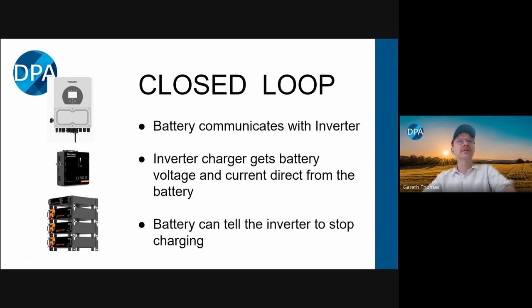The advantage in doing this is that when you're in the middle of the range, the charge current and the discharge current can be greater than when it's open loop. With open loop you're going to have to be more conservative with your values because they've got to be suitable for the entire way through the charge curve, rather than just in the middle. So you can get a bit more power out of the batteries if you're having a closed loop scenario. A lot of the time, that's not going to make a huge difference, but it is a design factor that you might need to take into account sometimes when you have not many batteries.